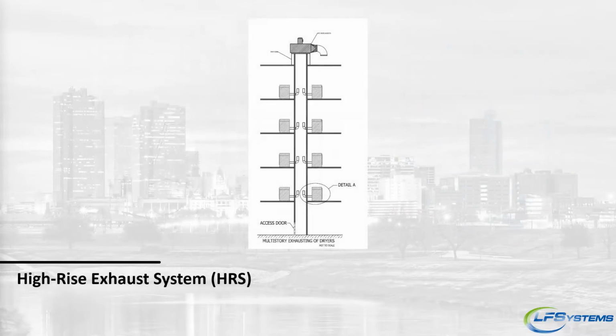So the other option that we can look at and we recommend is our high-rise exhaust system. This is a central shaft-based system. So instead of running those dryers, those hoods, the bathroom exhausts out through the sidewall individually, you'll now actually run them to a vertical chase that's running up through the building, picking up 1 or 2 dryers per floor or 1 or 2 kitchen hoods per floor, and running it up to a vertical termination.